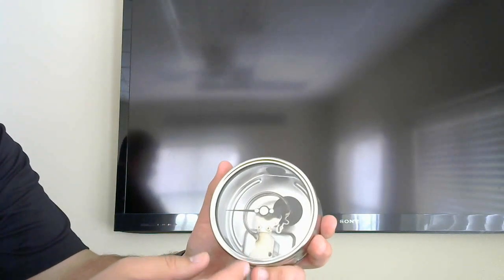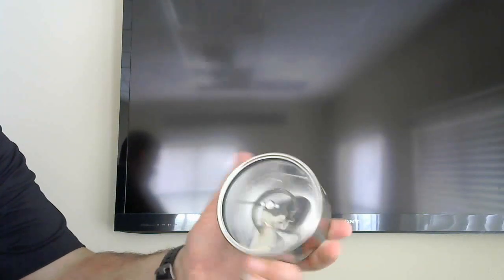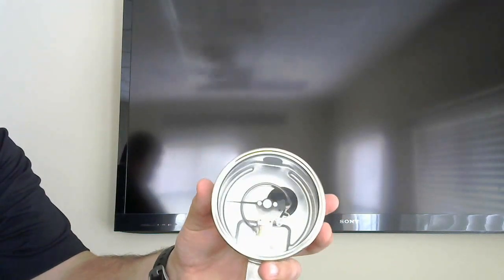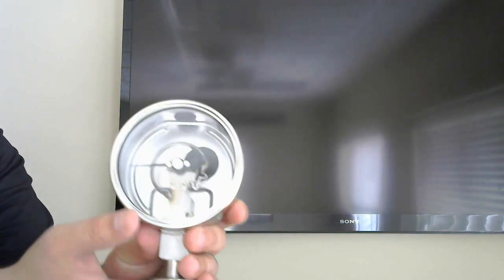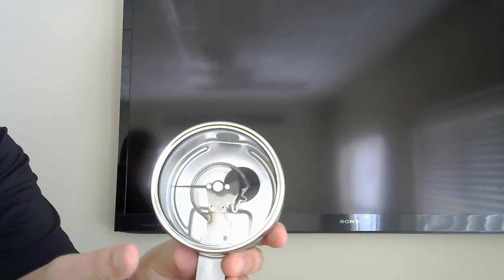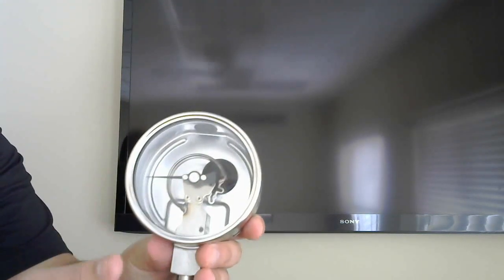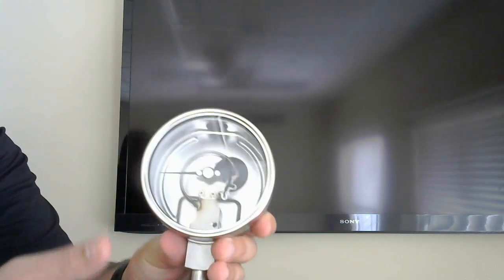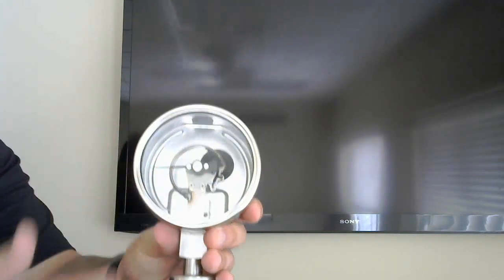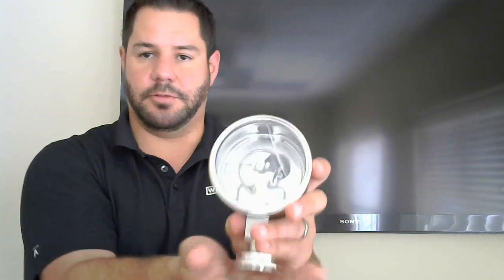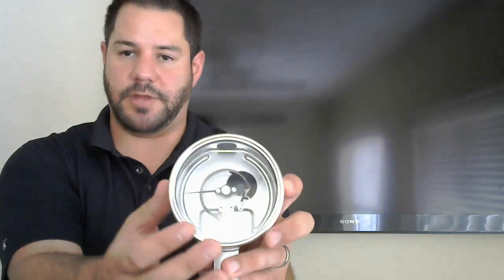What's special about WIKA is that they use complete stainless steel internals in their basic gauge, which isn't the industry norm - a lot of people still use brass internals. That's not good in the sanitary industry, because if the diaphragm gets damaged, product could reach those brass internals. So that's a great selling feature of WIKA's basic M93X.3A gauge: all stainless steel internals.